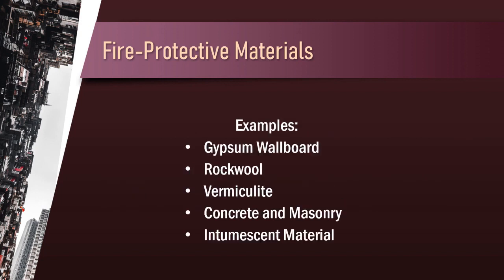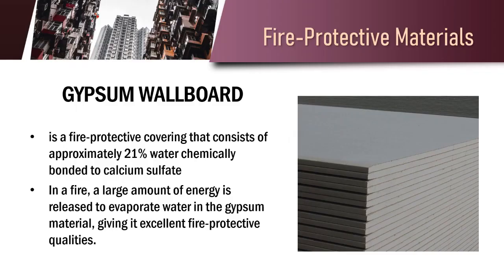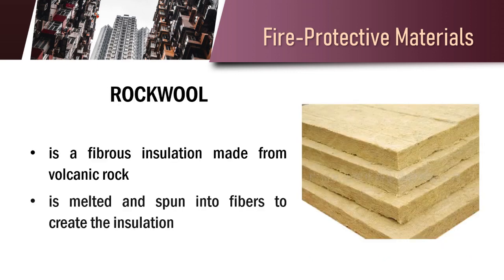Some examples of fire protective materials that are commonly used are gypsum wallboard, rock wool, vermiculite, concrete and masonry, and intumescent material. Gypsum wallboard is a fire protective covering that consists of approximately 21% water chemically bonded to calcium sulfate. In a fire, a large amount of energy is released to evaporate water in the gypsum material, giving it excellent fire protective qualities. Rock wool is a fibrous insulation made from volcanic rock. It is melted and spun into fibers to create the insulation.